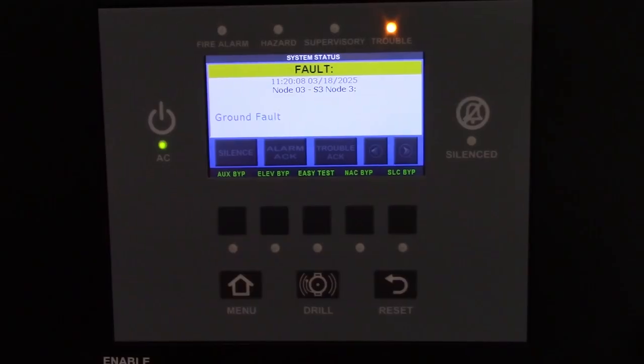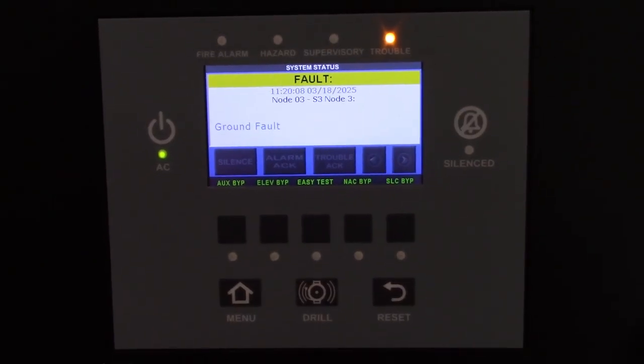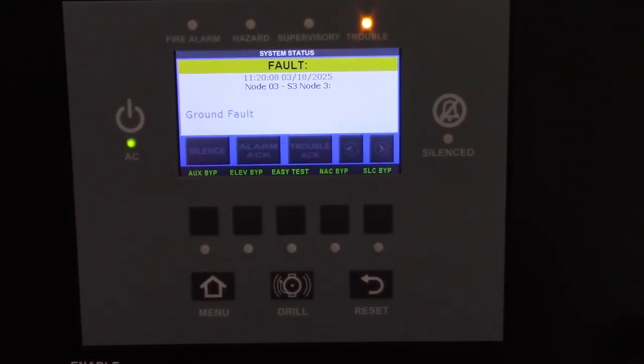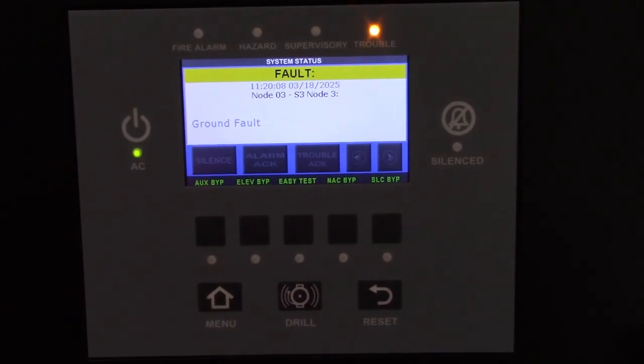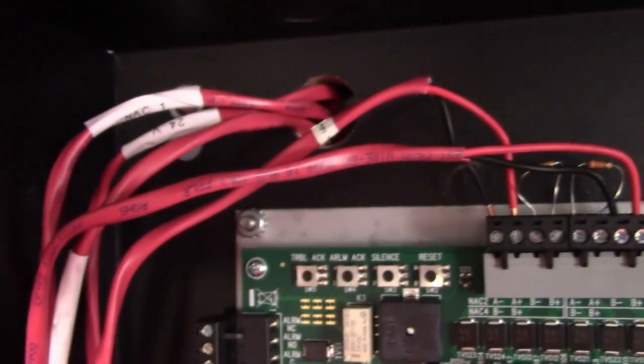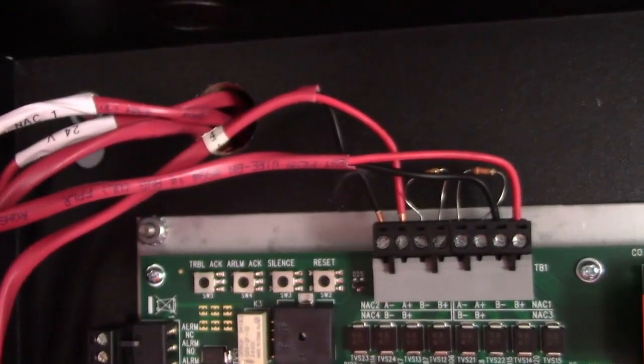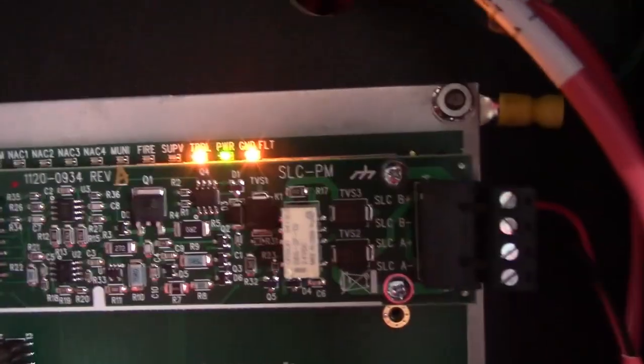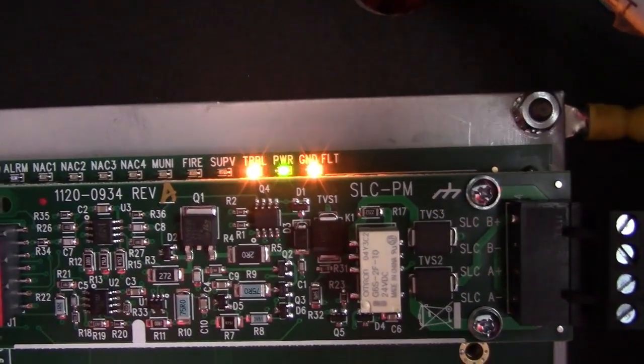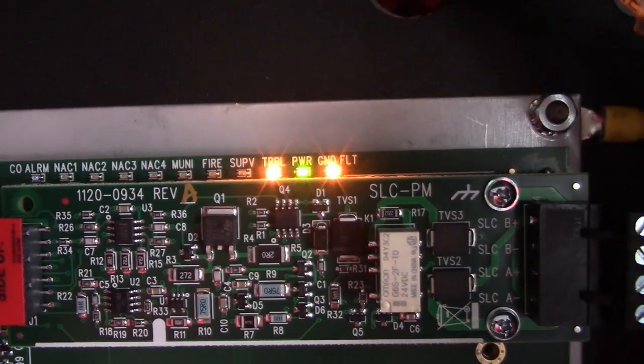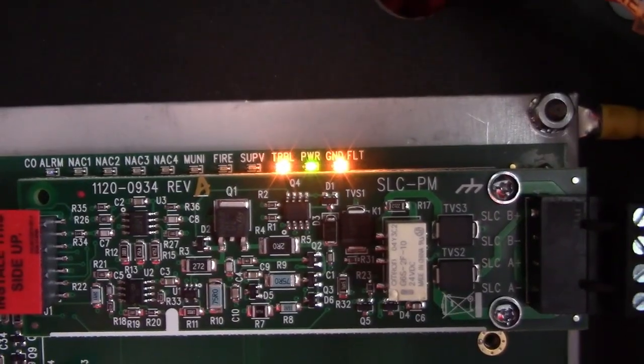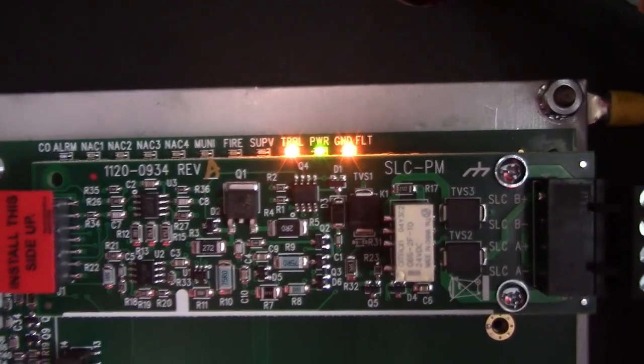We'll go back to this system here, which is in ground fault again. So we'll take a look at a few things inside the fire panel. When you open it up, you'll see that there's wires in different areas of the control panel that leave the cabinet. And that ground fault is on one of these circuits, but you don't know which one and the panel is not telling you. Additionally, we see we have the power light lit, the trouble light lit, and the ground fault light.